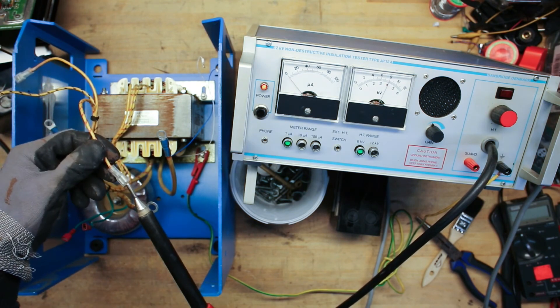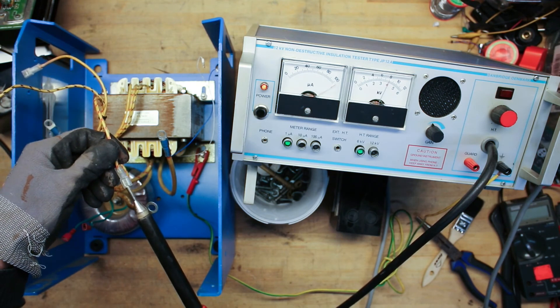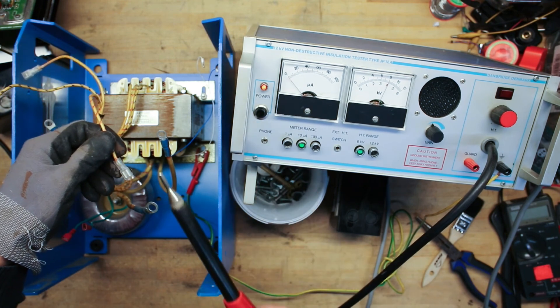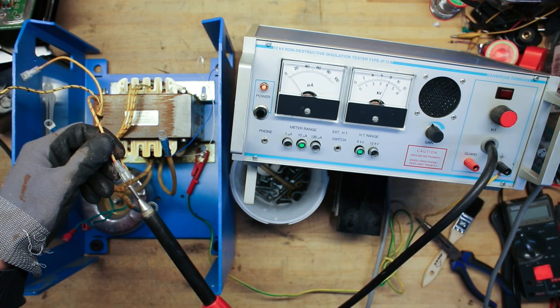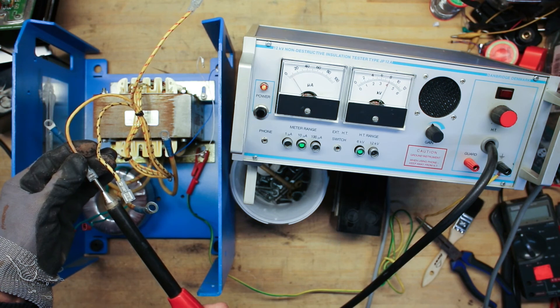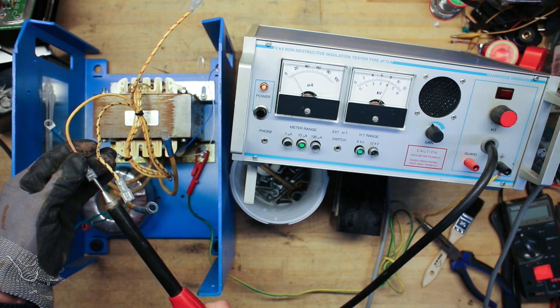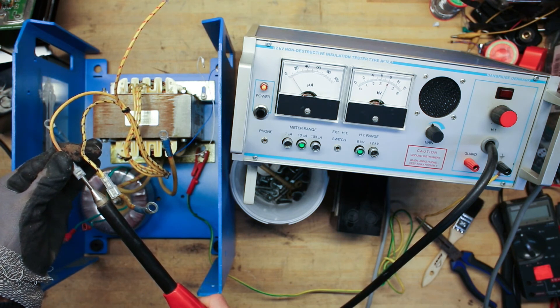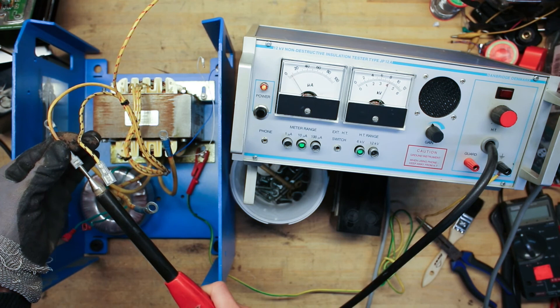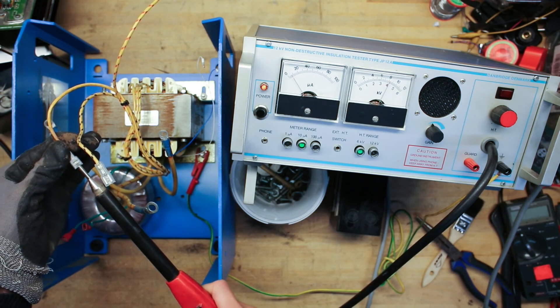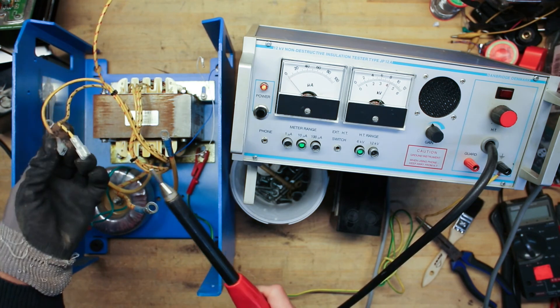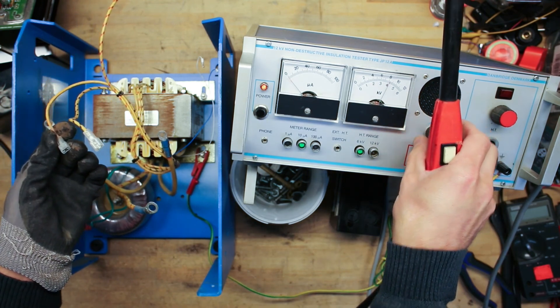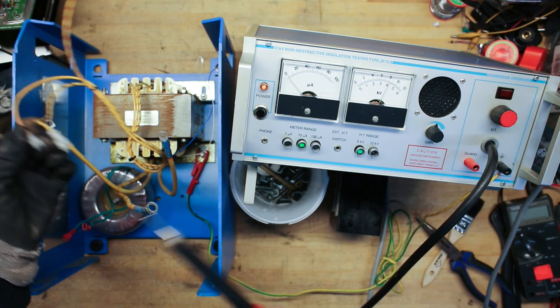So let's try the primary side. That looks bad right away. Even without the high voltage. Let's try higher scale. See that sounds bad. The clicking noises we can hear is actually flash overs to ground. So I think we have a defective insulation inside this transformer.